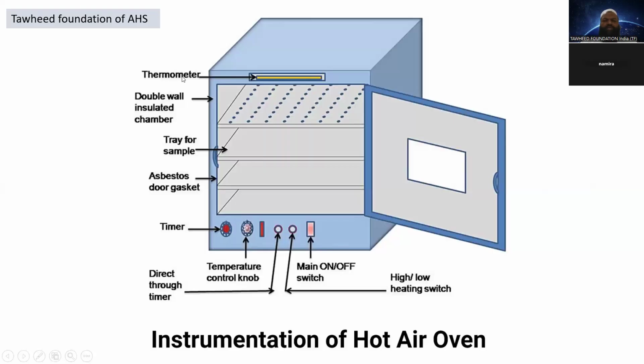All these things I'll explain one by one. We'll start with the thermometer. I'll tell the purpose as well as its function. The thermometer monitors and displays the internal temperature of the oven chamber to ensure accurate heating. Its placement is usually fixed at the top inside the chamber for easy viewing and precise control. Double wall insulated chamber. Its purpose is to maintain heat efficiency by reducing heat loss. The double wall construction ensures the inner temperature remains stable while the exterior stays cooler. Its function is that the insulation minimizes energy consumption and protects users from heat exposure.